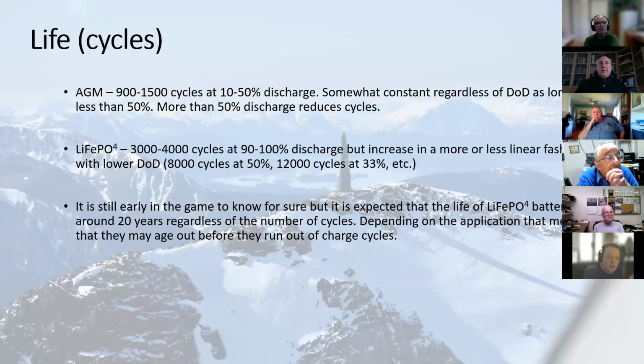Next, I'll talk a little bit about the life or the cycles available. A typical AGM or sealed lead acid battery, depending on the manufacturing and the process, is 900 to 1500 cycles in that 10 to 50% depth of discharge range. And it's somewhat constant as long as you keep it above that 50%. If you discharge them more than 50%, you do start to impact the number of cycles available. Lithium iron phosphates are typically 3,000 to 4,000 cycles at 90 to 100% of discharge. And the interesting thing, though, is that they increase in a very linear fashion with a lower depth of discharge.